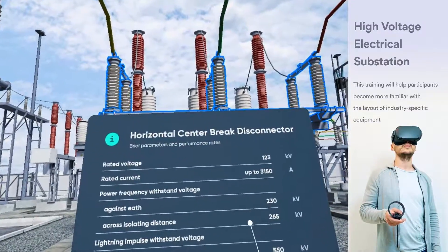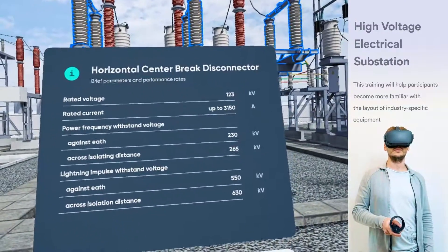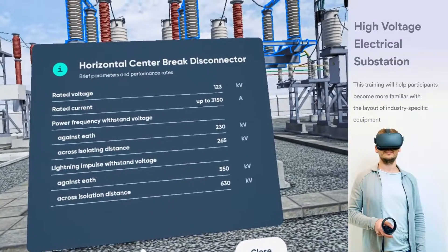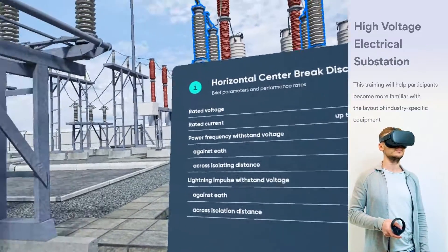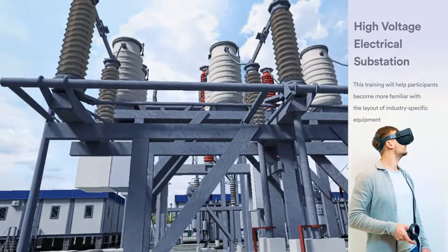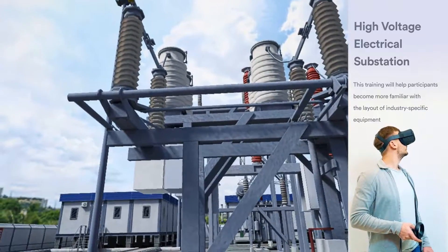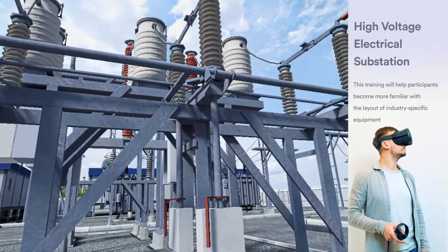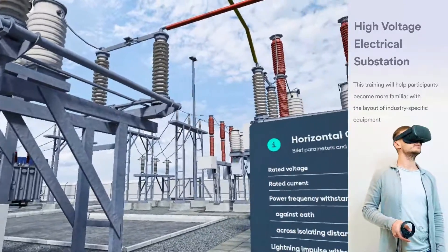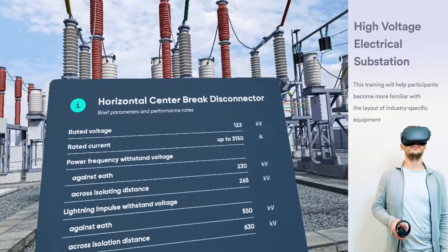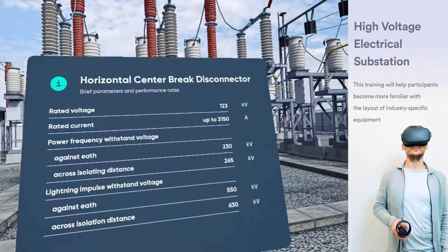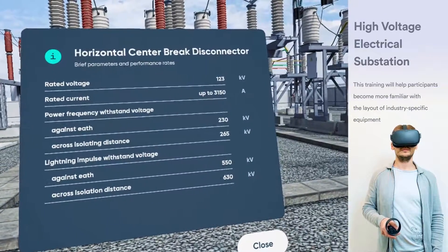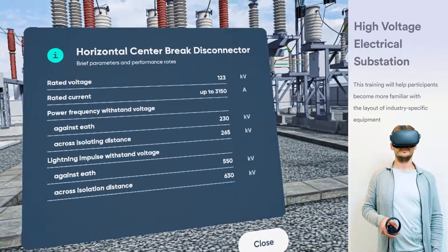Center brake disconnectors are designed for operation in outdoor substations. They are used for metallic isolation of systems by creating an open-position, safe and visible isolating distance. The center brake disconnector is formed by three poles, operated simultaneously either by a single operating mechanism and mechanical linkages between the poles, or by one mechanism for each pole.